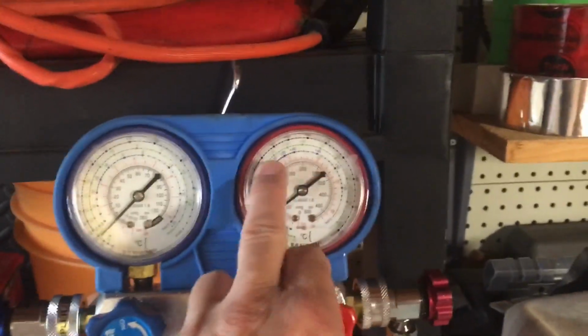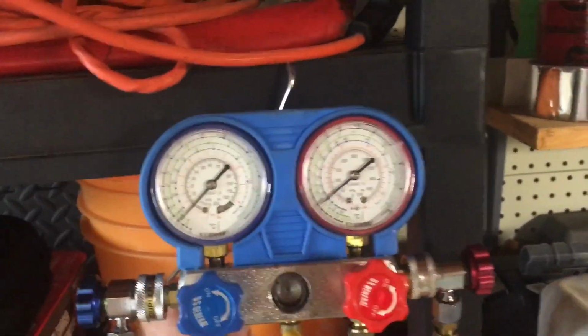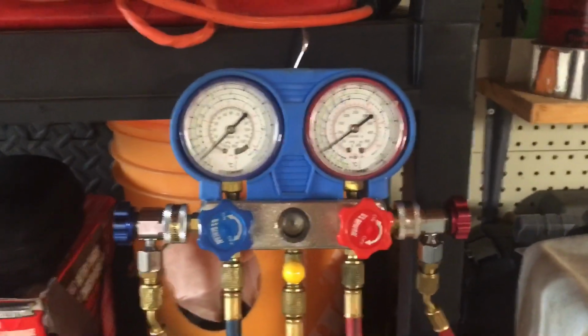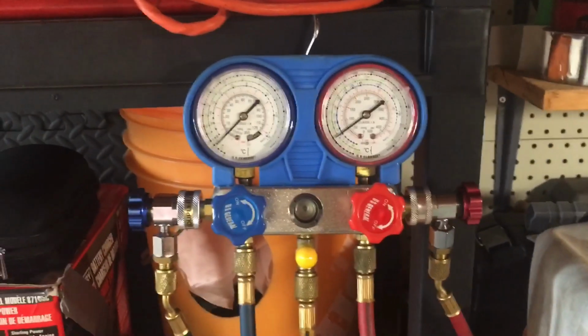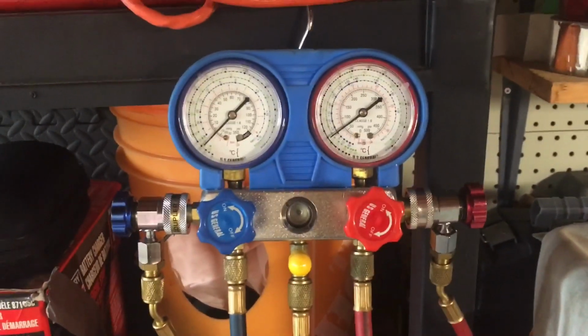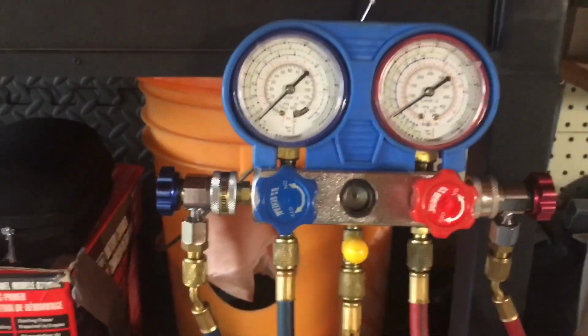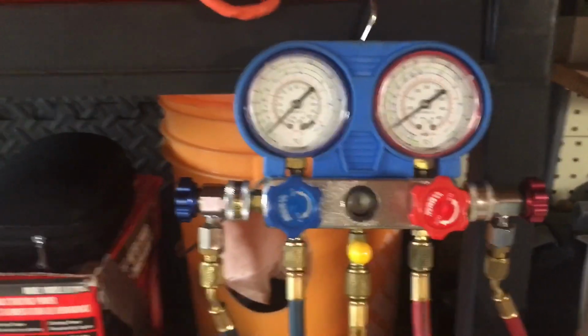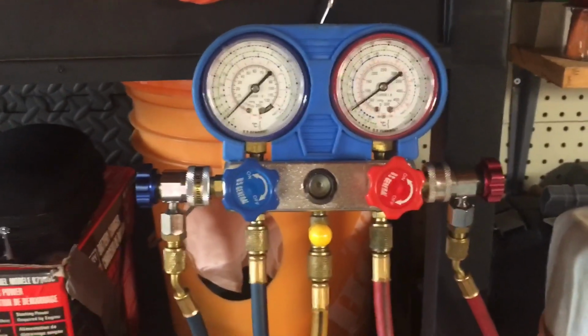Dig, if you will, what I'm going to try, guys: with the nitrogen hooked up, I'm going to pressurize the system to, say, 150 pounds or so, whatever a reasonably high pressure would be, to kind of force this thing to leak. And then what I'm going to do is disconnect the coupling. Well, disconnect the coupling — how the hell are you going to monitor the pressure drop?